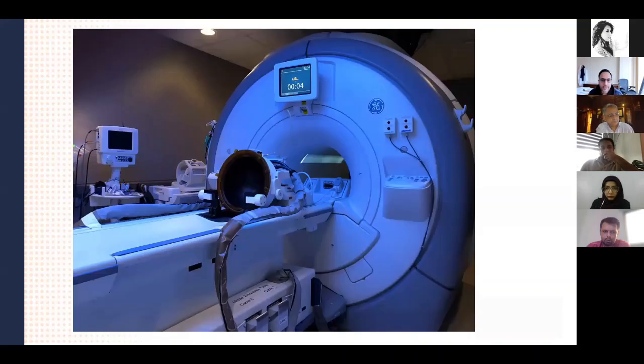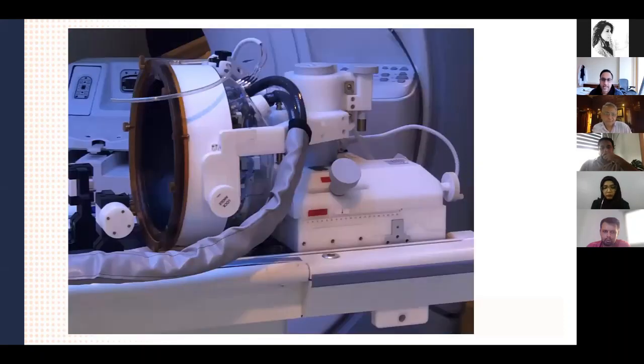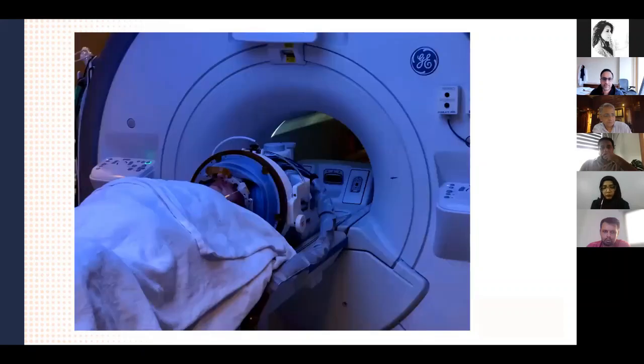So this is a picture of the focused ultrasound machine within the MRI room. You can see that the transducer head frame has 1,024 elements of ultrasound rays that can converge to a point that needs to be treated. This is looking at the actual stereotactic mechanism, and there are XYZ coordinates that can be adjusted in order to target precisely, with millimeter accuracy, where you need to target for your treatment, whether that's with high intensity focused ultrasound or low intensity focused ultrasound.